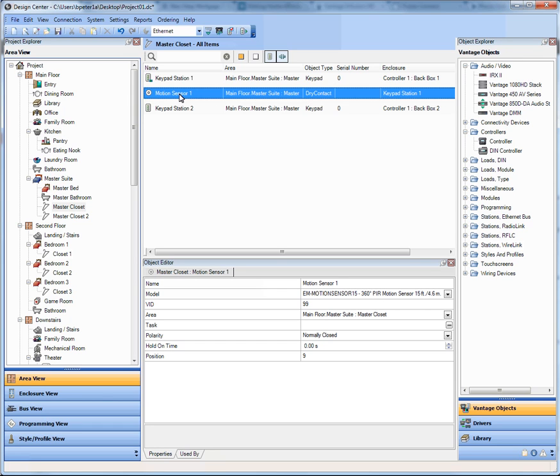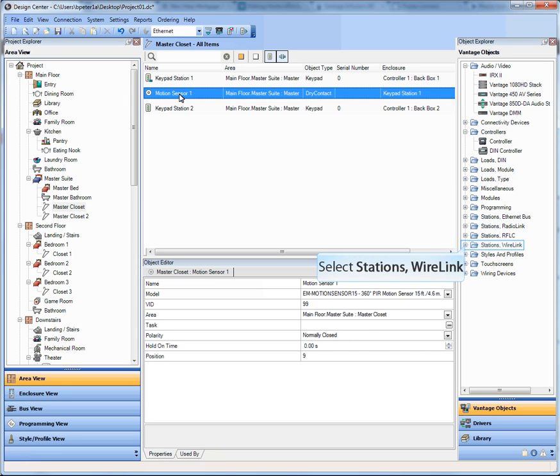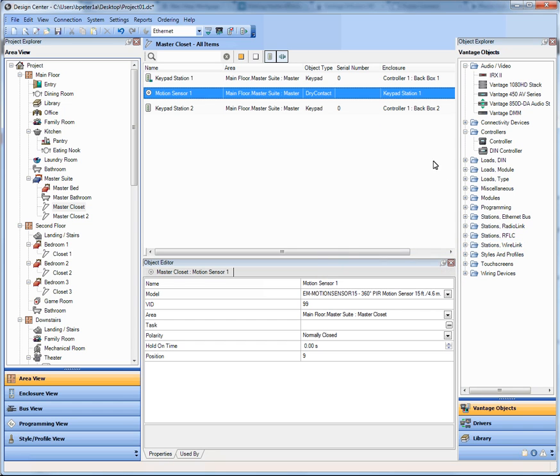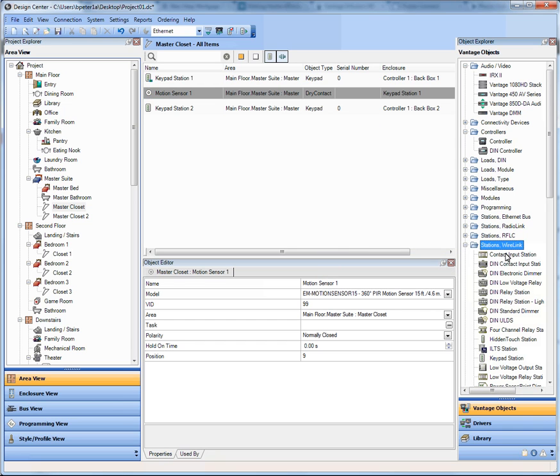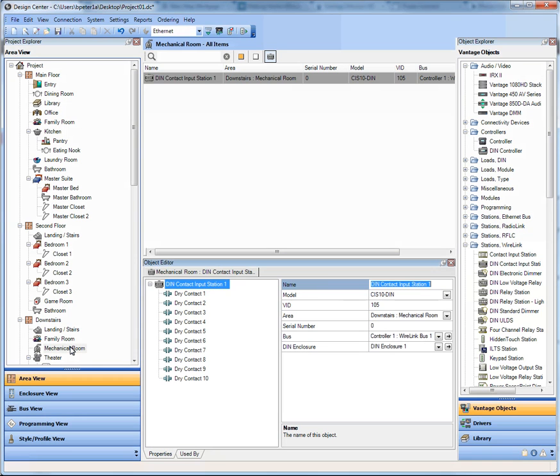Let's say maybe we aren't adding a motion sensor per keypad. Let's say we're going to add a contact input station for motion sensors into the mechanical room to do the rest of the house. So what I would do is I would go to my stations, wire link, and I'm going to take a DIN contact input station, drag it into the mechanical room, and now here's my ten contacts that come with each of those.